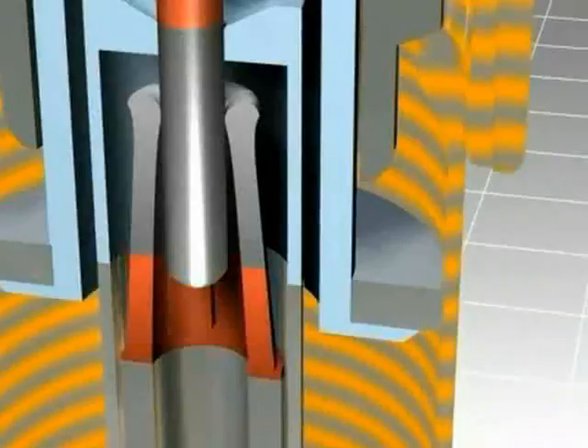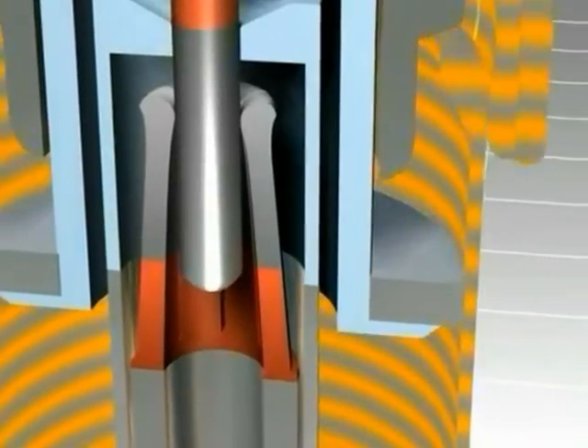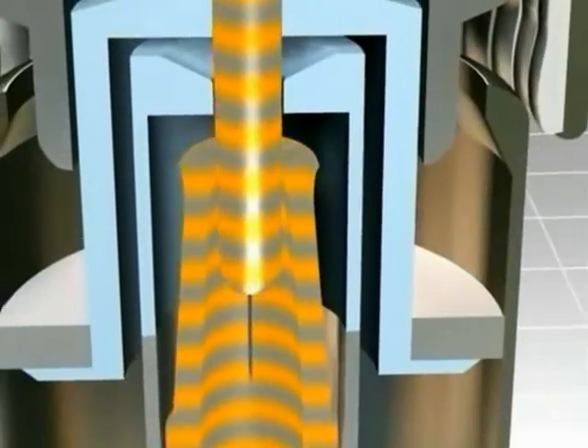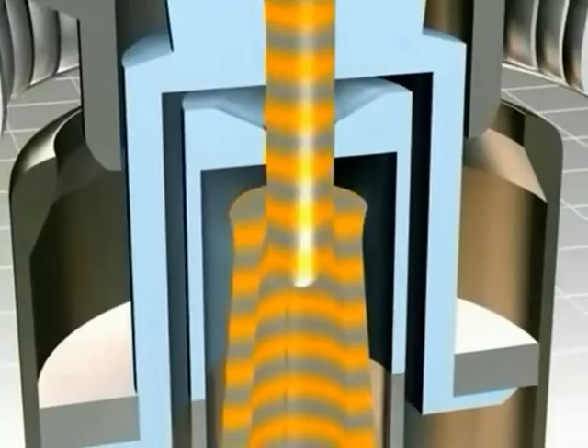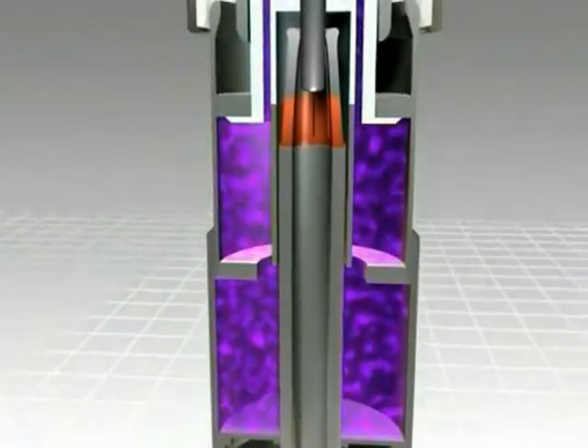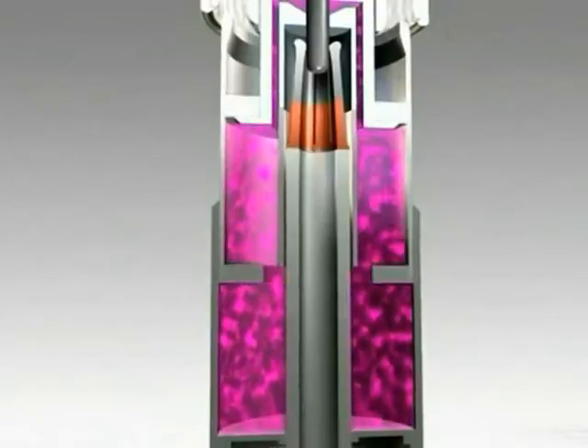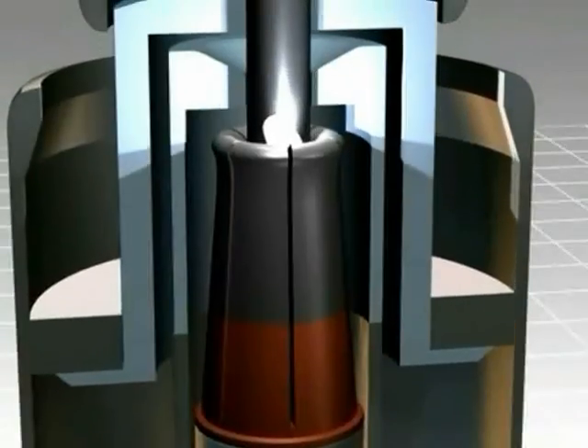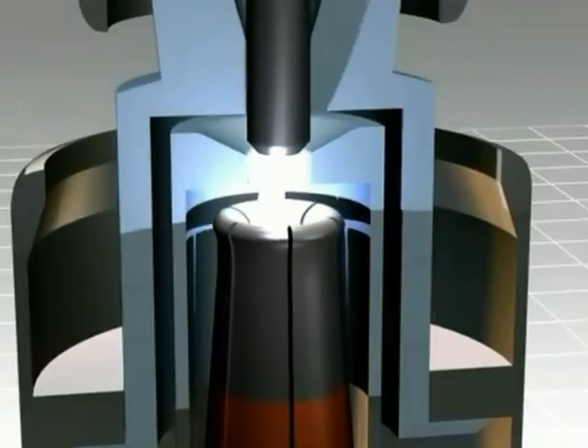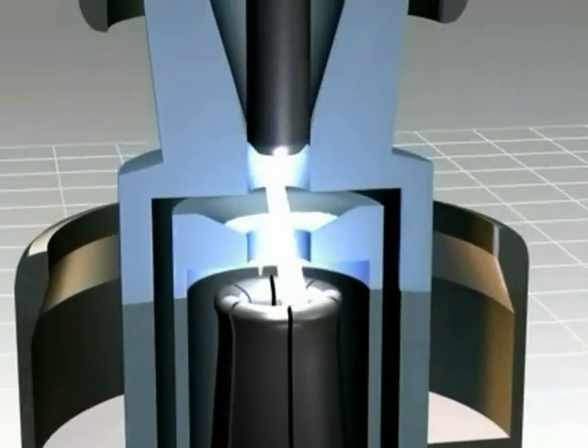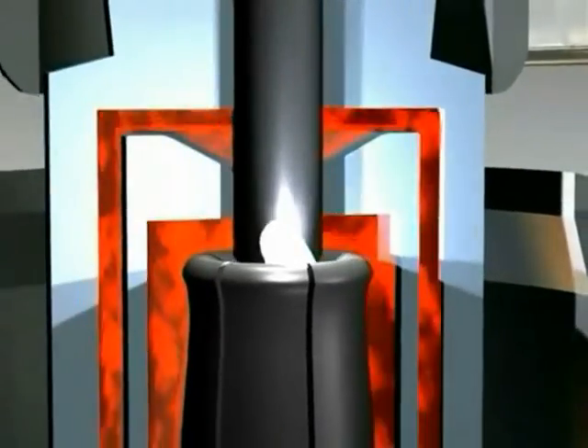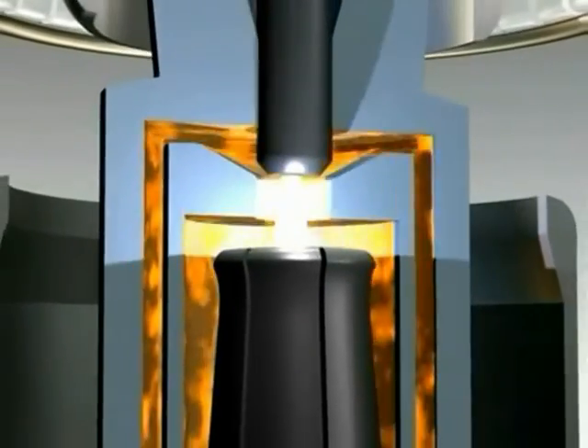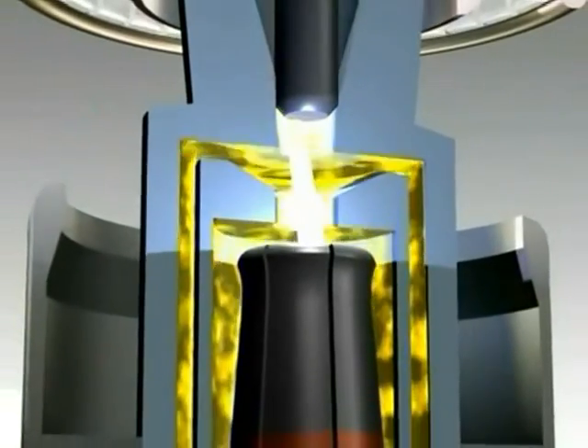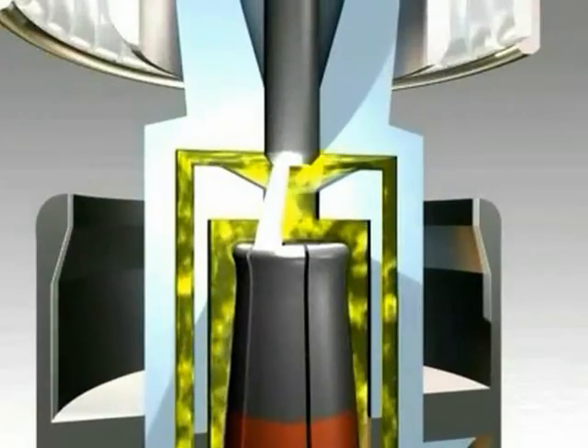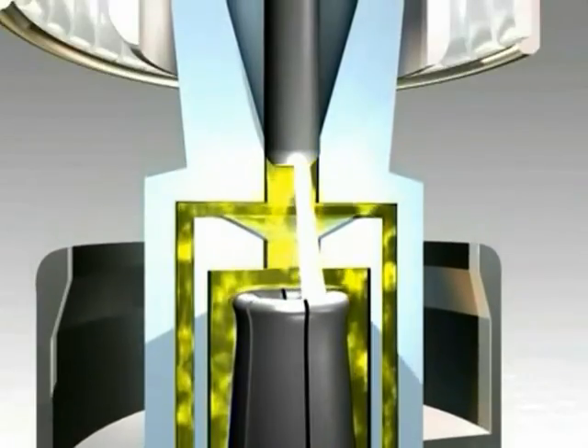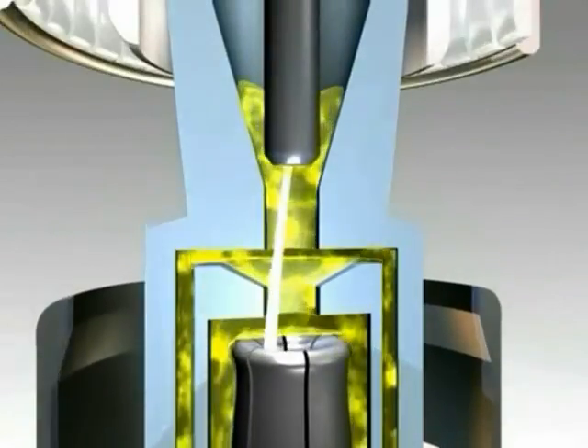During the breaking of operating currents, the main contact opens first, but the current still commutes through the arcing contact, which remains closed at this stage of the switching process. This avoids erosion of the main contact. During the further course of opening, the arcing contacts open and an electric arc is drawn between the arcing contacts. At the same time, the contact cylinder moves into the base and compresses the arc-quenching sulfur hexafluoride. This gas compression generates a gas flow through the contact cylinder and the nozzle, to the arcing contact. This way, the arc is extinguished.